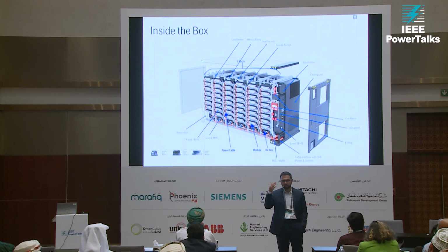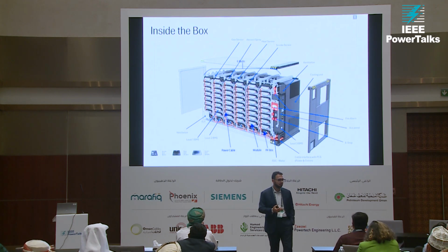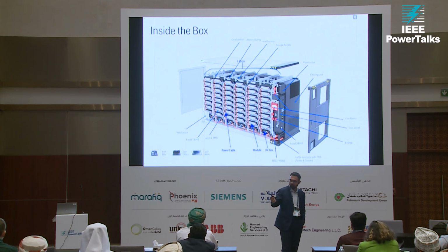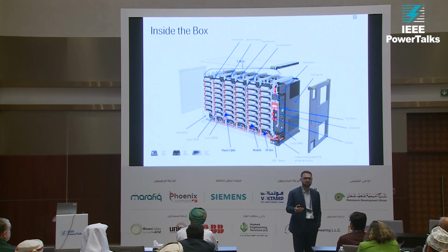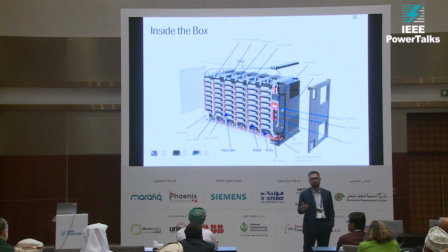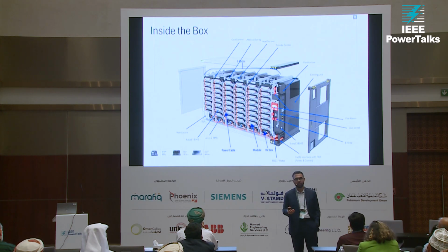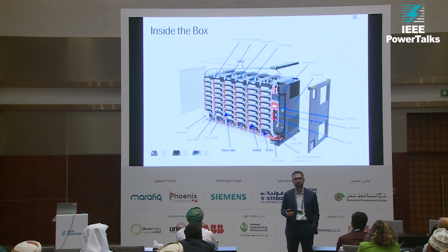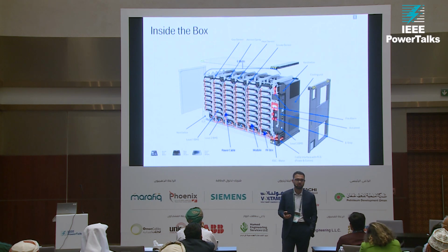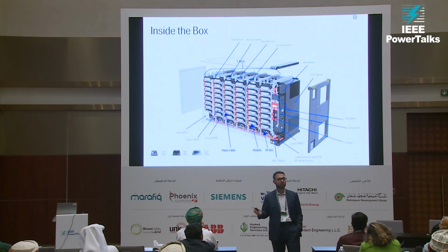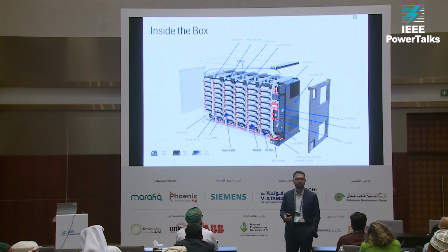I know there's this mindset in the market that battery systems are expensive. They used to be expensive. Just to give you data points, my first installation 12 years ago, we were buying batteries for about $1,000 per kilowatt hour. That's very expensive. The most recent systems we've bought are closer to $100 per kilowatt hour. So quite a change, and we see the industry even improving year over year on that.